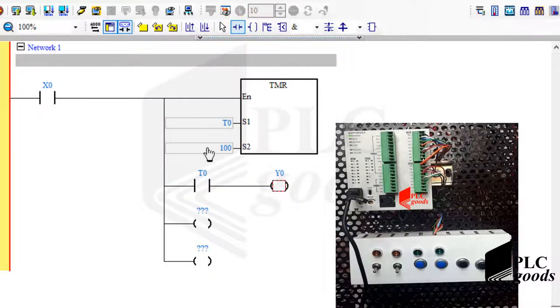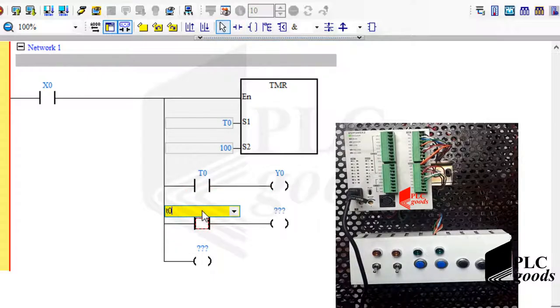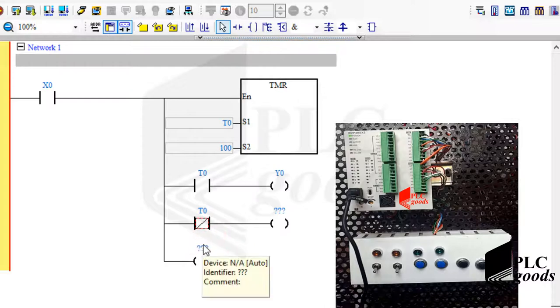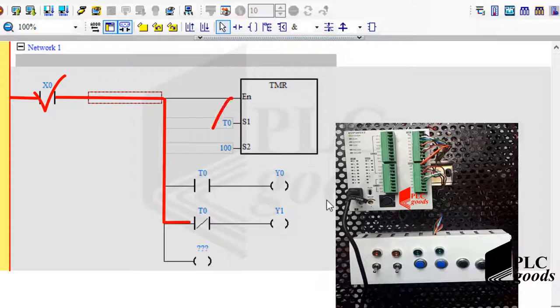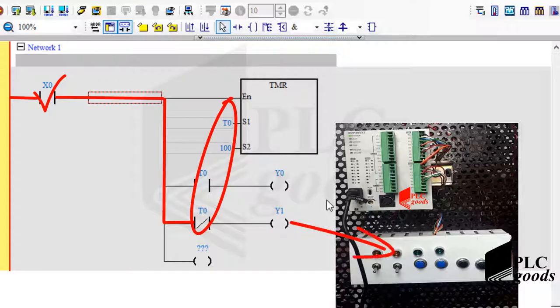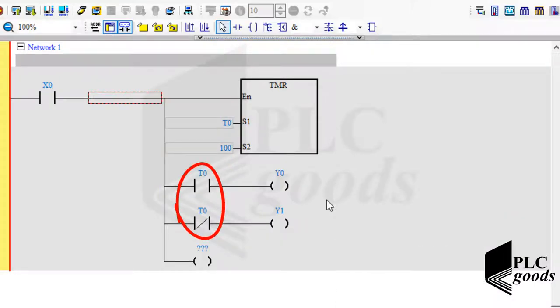I can also use a normally closed contact to turn on an output. When the first digital input is enabled, the PLC will turn on the second LED, but after 10 seconds this contact will change its state to open. So the second LED will be on only while the timer is in timing mode — until it reaches 10 seconds. As you know, normally open and closed contacts have only two states: open or closed. Therefore, when we use T0 for these contacts, the PLC automatically uses the timer mode to determine their state — whether the timer has reached its final time or not.